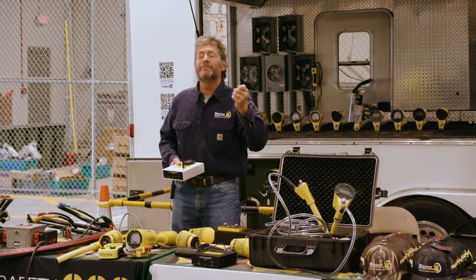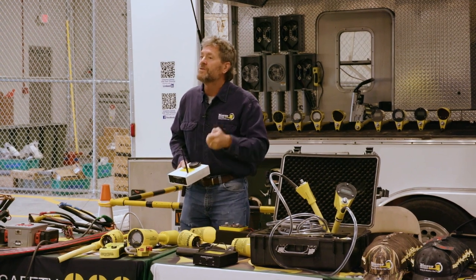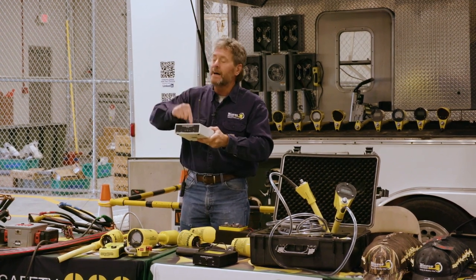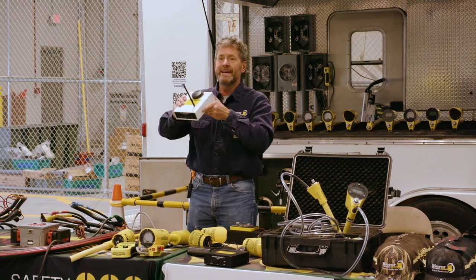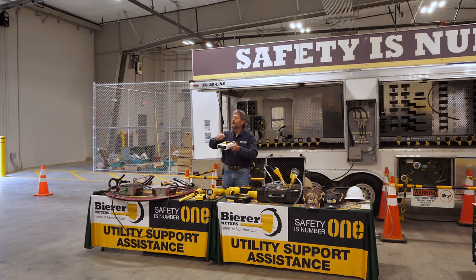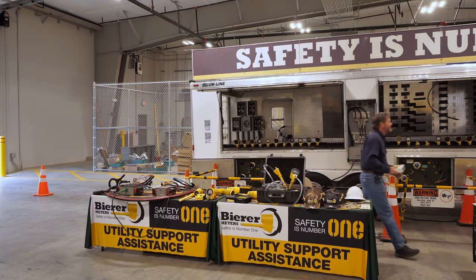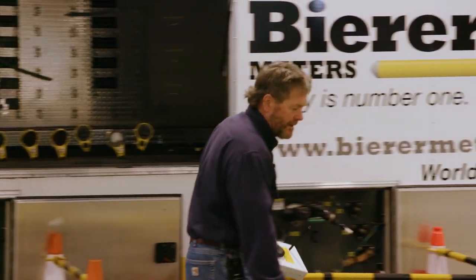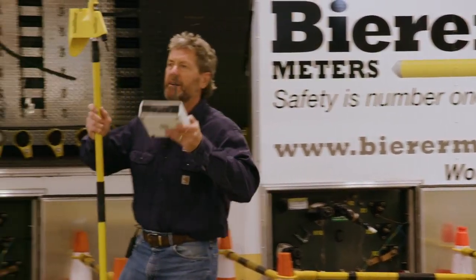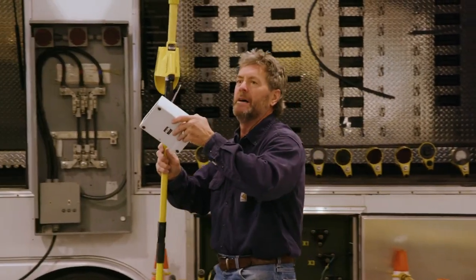Then you simply turn on your Bluetooth. When you turn on the Bluetooth, it links up to your field unit, and when it does, the white light here goes solid. When the white light is solid, this becomes your A phase reference anywhere in the field. So when you're phasing, all you need to do is be within 300 feet of this antenna and this antenna.